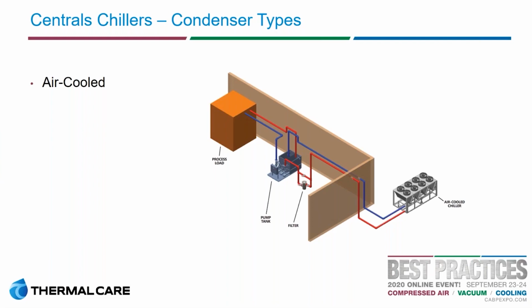So for capacities of large central chillers, that heat is always going to be rejected outside of the building. In this case, the entire chiller itself is packaged out there. So that contains the fans, which are rejecting the heat ultimately to the atmosphere, but also it contains that complete refrigeration circuit. So what happens here is you can kind of see that figure 8 here. It's a little harder to see with the routing of the piping, but we have that red piping that pulls from the tank and pumps out and through that wall and then into the chiller. It then returns cool now as that blue line and returns to the other side of that tank. So that's that figure 8 we talked about.